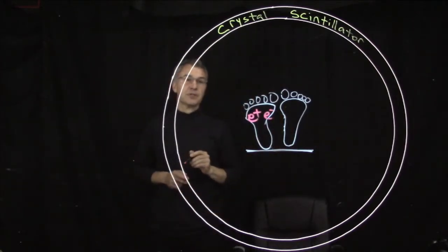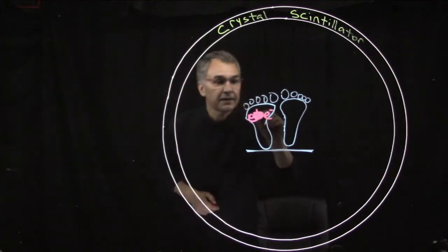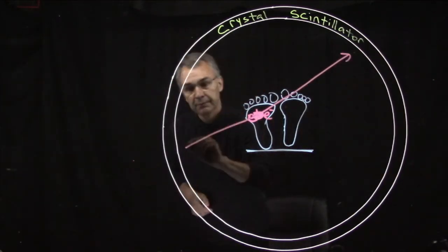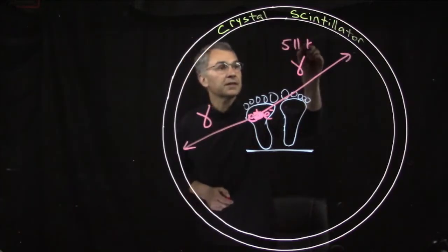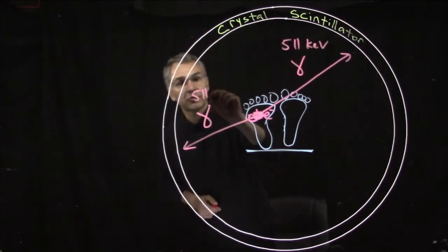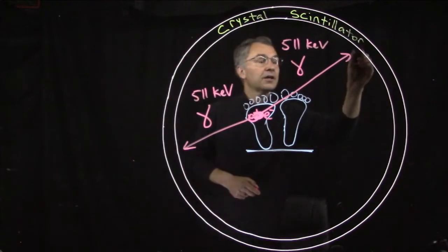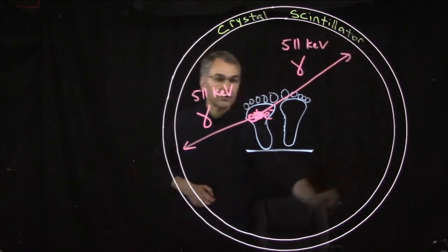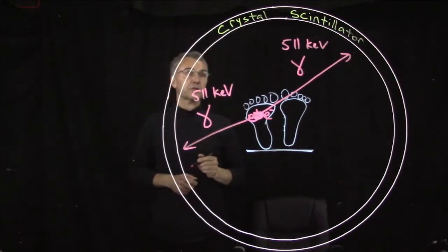We said that happens within about a millimeter, and they then annihilate, and the result is two back-to-back X-ray photons, each of which has an energy which is equivalent to the rest energy of an electron or positron, 511 keV, and somehow we want the PET scanner to be able to detect the passage of these two back-to-back X-ray photons.